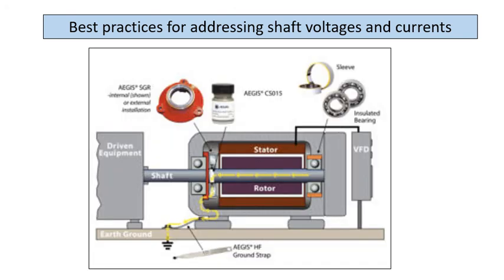This is something I found on Aegis' site. Sorry about the really bad quality picture, but I couldn't find a better one. This is what they call an Aegis HF grounding strap. It might be made of Litz wire or something, continuously transposed wire, whatever, to have a lower impedance at high frequencies. And then what I found very interesting, this little bottle is colloidal silver. They actually recommend coating the shaft where your brush sits with colloidal silver. You can go and look at the website.